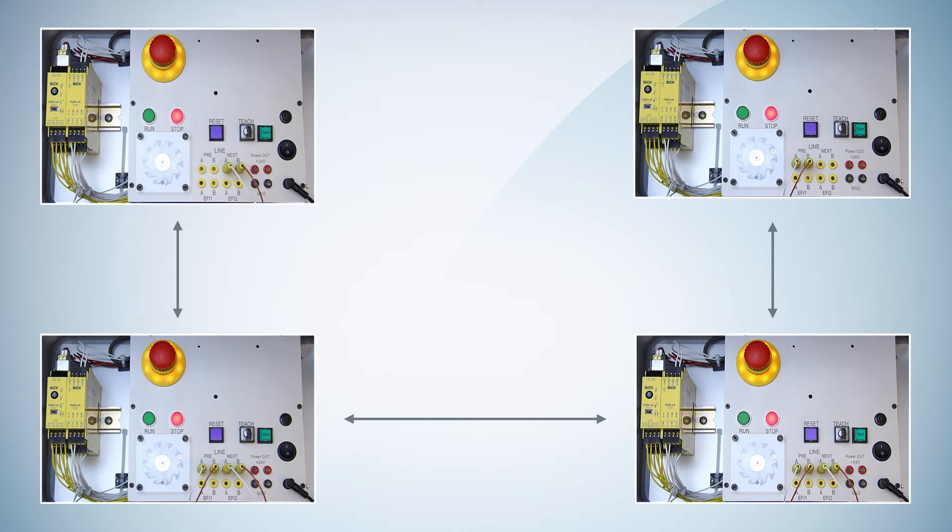The arrangement of the stations in the Flexi-Line system must be confirmed during commissioning via a TEACH process. Once you change something within the topology, the Flexi-Line communication will stop. Then you only have to confirm the new arrangement before the communication can start again.